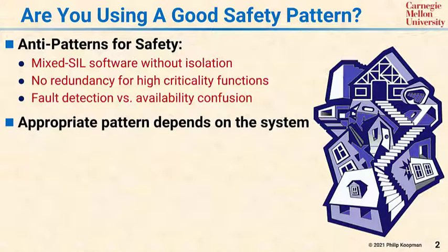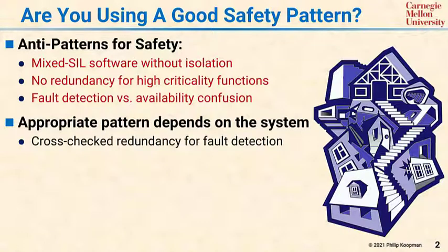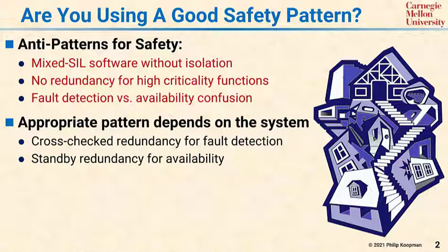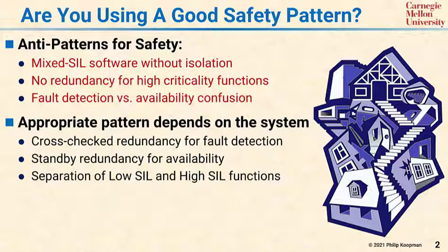The appropriate pattern for safety in your system depends on your particular application. However, there are some standard mechanisms and pieces that you can put together to assemble the right architecture for your system. The first piece is cross-checked redundancy, which can be used for fault detection. The next piece is standby redundancy, which can be used for availability. And the last piece is separation of high and low SIL functions, with each SIL having its own isolated CPU.